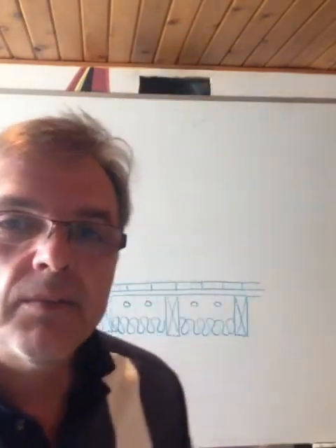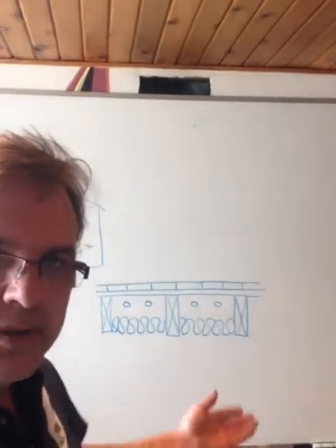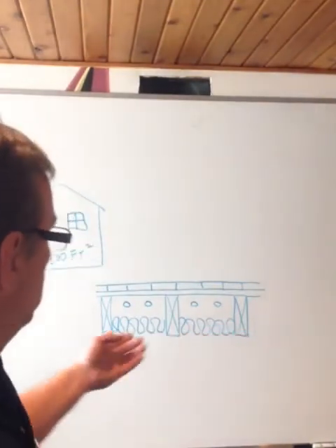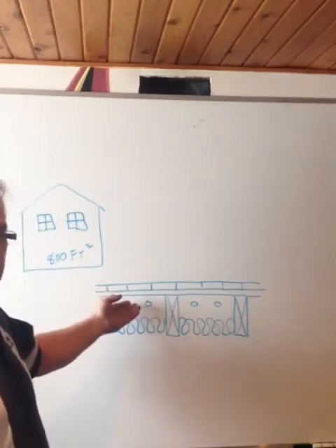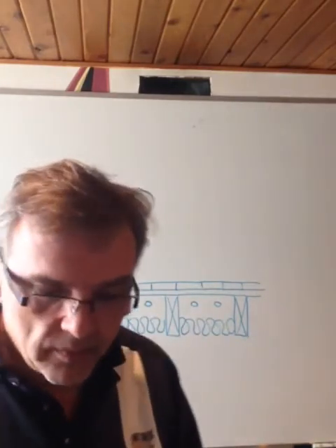I want to talk to you a little bit today about a problem call I keep getting, and that call is, my radiant heating isn't working. What's wrong? So I go out on the job site and I look around and I see something like this. Tubing installed under the joist cavity, insulation, tubing is free hung, everything seems to be pretty normal. Now, that can work in some places, but it doesn't work so good in cold climates. So I just want to run some numbers by you and have a look at why that's not working.